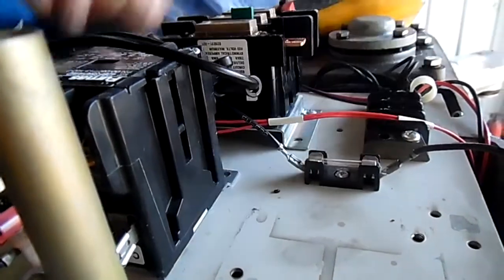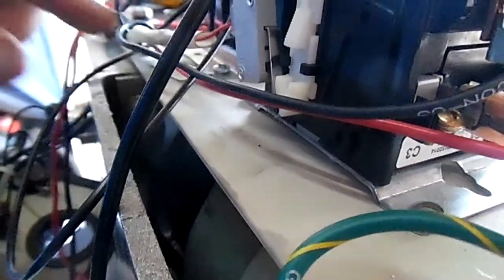The nice thing about Hobart, they give you enough room. These are both quick connect couplers. You can disconnect it here, keep the wire from the switch and put it right on your auxiliary, doing away with the two red wires. If you need to, you can always make a temporary jumper. As soon as you turn it on, you'd be bypassing your systems.